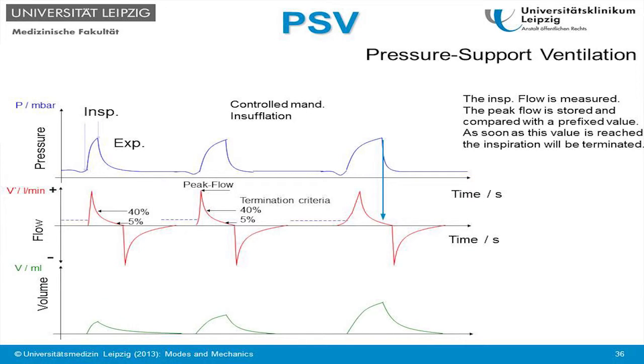Another development is pressure support ventilation. Pressure support ventilation can be used with a flow sensor or with a Graseby capsule, which means that the patient gets not only control over the start of the inspiration of the machine, but also over the end of the inspiration. So you see that the inspiratory time changes up here, which is determined by the inspiratory flow. When the inspiratory flow goes below a certain threshold, then the machine will terminate the inspiration. And if the inspiratory flow takes longer, then the inspiration of the machine takes longer. So with this type of support, you don't have to set an inspiratory time on the ventilator, because the ventilator will terminate the inspiration when the patient feels that the inspiration has been long enough.